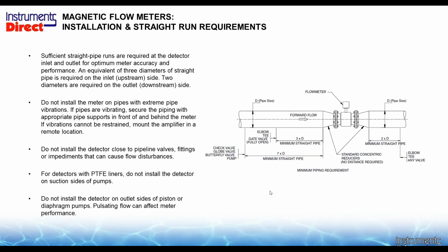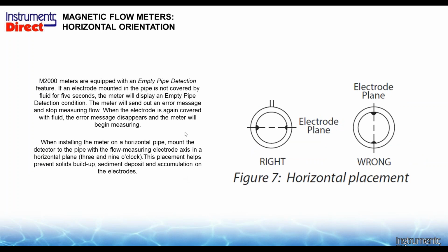Some other interesting points. Should you have a Teflon liner, you probably don't want to install this on the suction side of the pump, because we don't want to loosen the liners in that application. Depending upon your particular application, it's something to consider. This device is equipped with empty pipe detection, which is very helpful when there's no flow in the pipe. Basically, when this device doesn't see any liquid between the two electrodes for about 5 seconds, an empty pipe warning will come on. After that, it will stop reading flow. When there's again a connection between these two, it will begin to measure flow again.